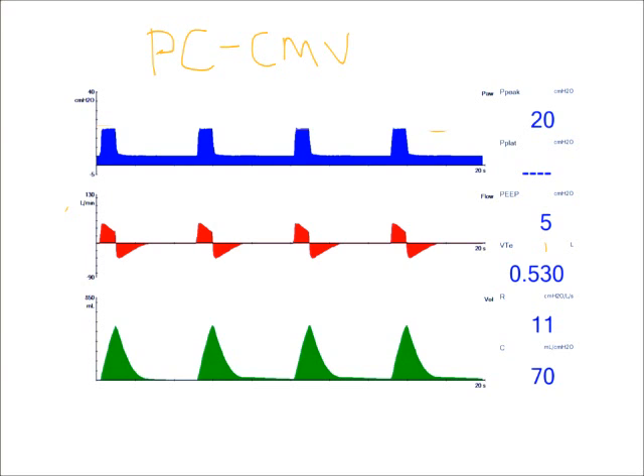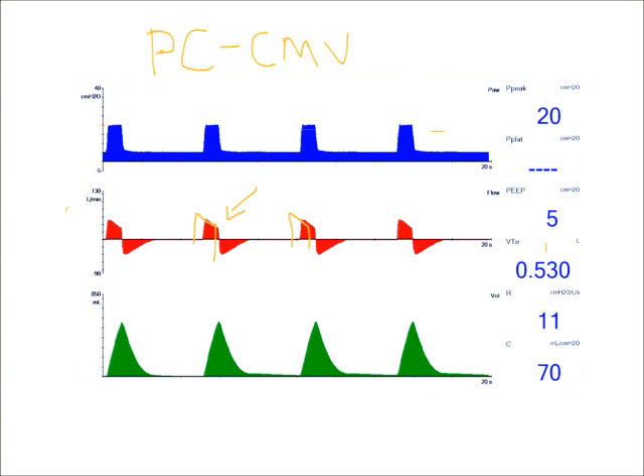So what I should evaluate is my inspiratory flow waveform. And I want to make sure it's fully decelerating. So I'm looking at my waveforms down here and I'm looking at my inspiratory flow. And you notice my flow stops there. So my flow is not fully decelerating. My flow is ending there.